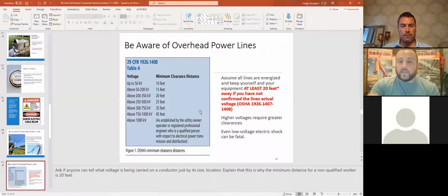Then there's the OSHA standard of 20 feet if you're not sure of the energized facility voltage. But that 10 feet doesn't apply if you get near some of our transmission voltages -- obviously the distance increases. Once you get up near 500,000 volts, you're actually up around 35 to 38 feet that you need to maintain from our 500 kV transmission lines.